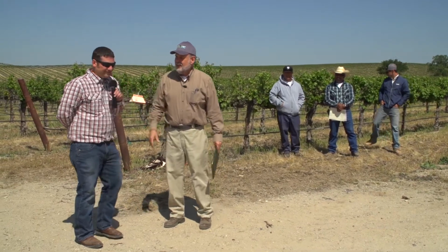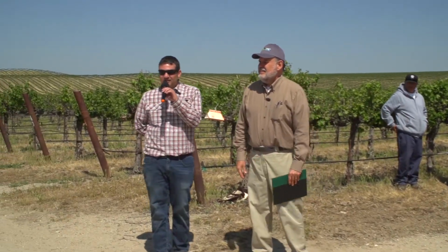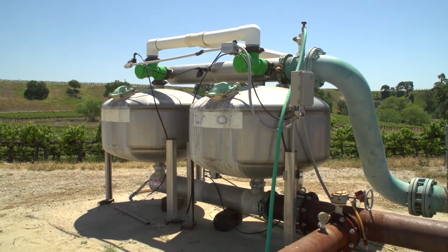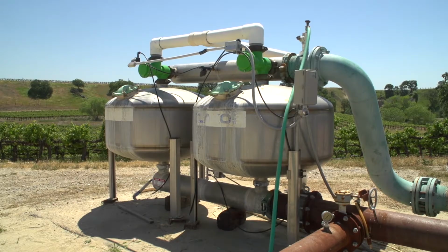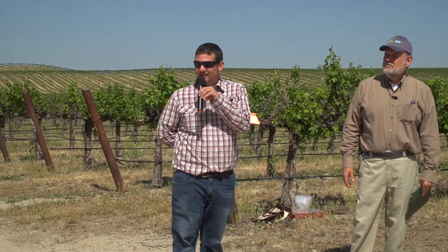Great. Yeah. Okay, so moving on to those filters. Those are definitely those sand media filters in there. Probably more indicative of an older install. You're going to see different types as you go around. But what kind of types do you guys have? If you want to shout them out? Sands. So I see a lot of sand, and the newer types I see are the cleaned tubular screens. So really with that sand media, you want to be replacing sand to keep that thing working right.